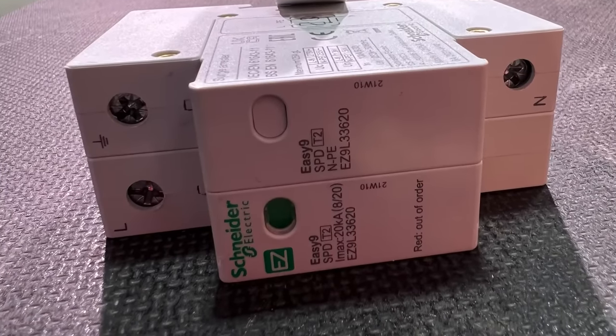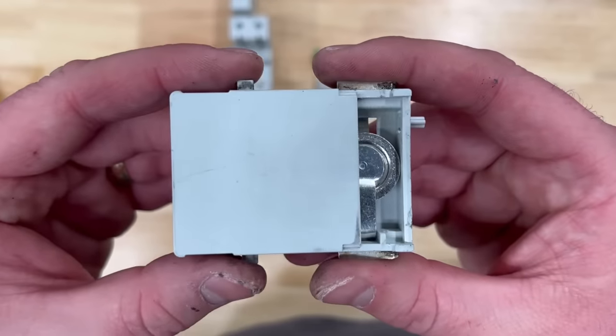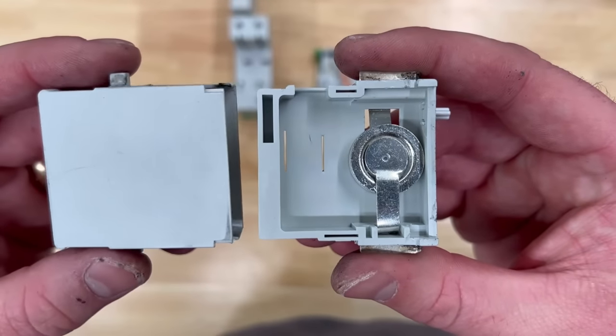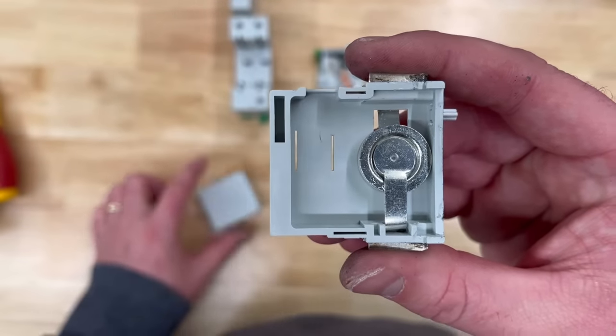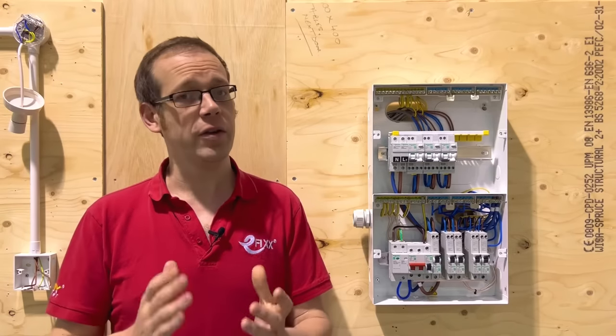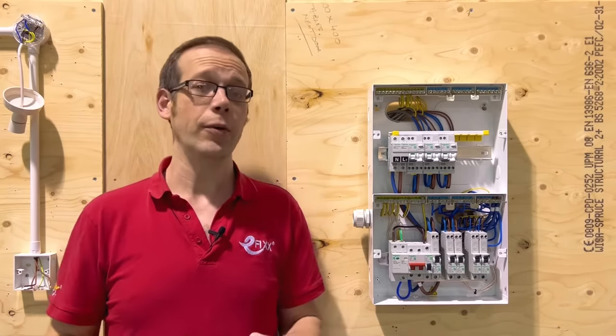An SPD usually contains either a gas discharge tube or a metal oxide varistor. Both of these devices change their resistance depending on the voltage applied to them. So when the voltage goes up, the resistance lowers.